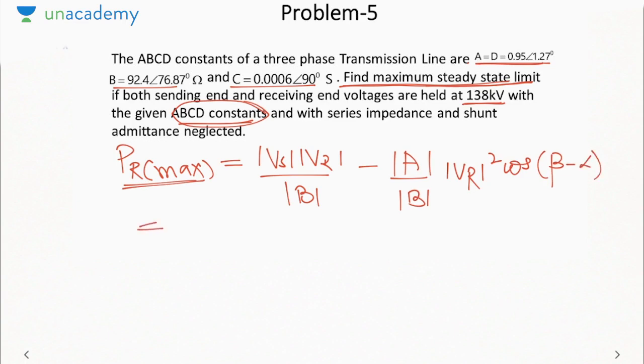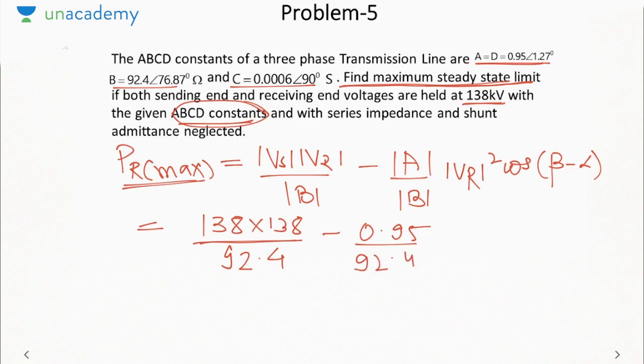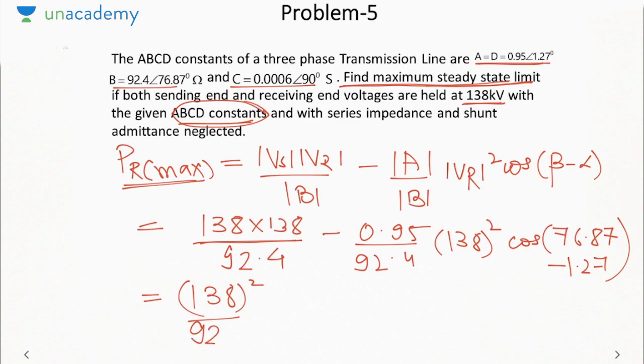Now I told you if you substitute both line voltages you will get three-phase power directly. So 138 into 138. I am not taking the factor of kilovolt, so that power will directly be in megawatt: 10 raised to 3 times 10 raised to 3 gives 10 raised to 6. Divided by 92.4, minus 0.95 into 138 square cos of 76.87 minus 1.27. You can take 138 square by 92.4 common to simplify the calculation: 1 minus 0.95 cos 75.6. So this comes out to be 157.4 megawatt.